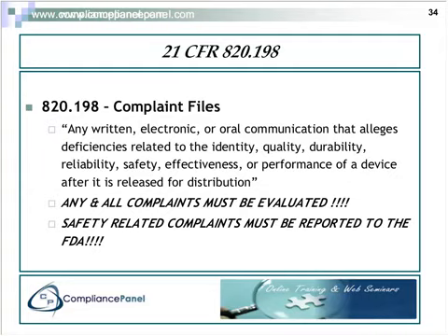You may not even be in your facility, but you may hear somebody say, well, my friend was at the hospital and they used this device on him and it didn't work properly, and you may know, well, that's what they make at my facility, so that could constitute a complaint. So it's not just a certain individual in your organization who can receive it. They may be the individual who coordinates the information once it's received, but anyone in your organization can be a recipient of a complaint. And you must have a very stringent procedure in place on how these are evaluated and investigated.